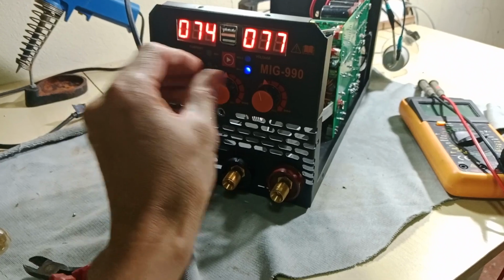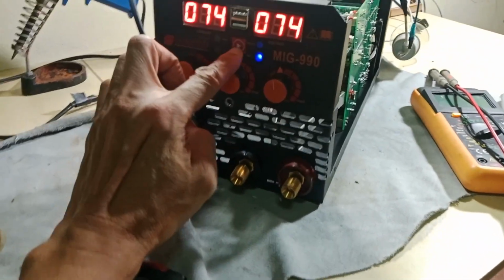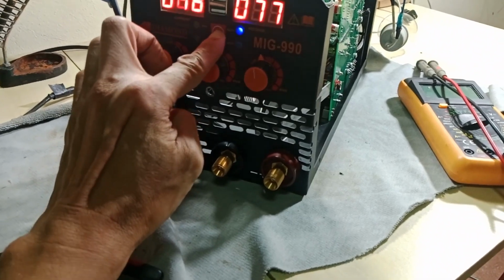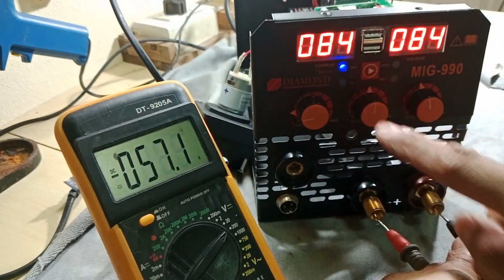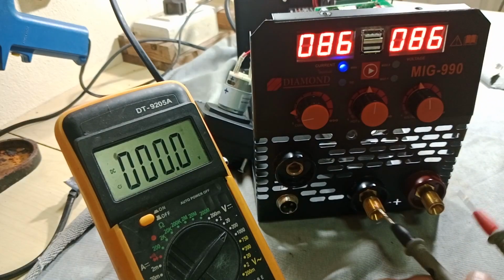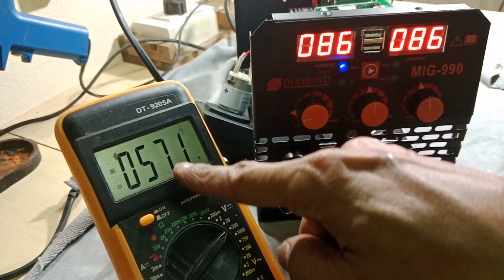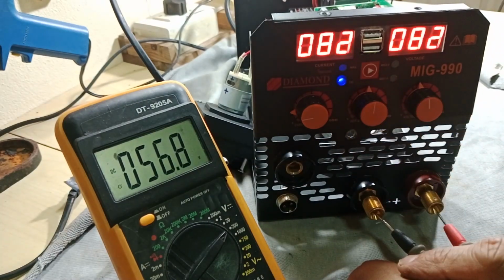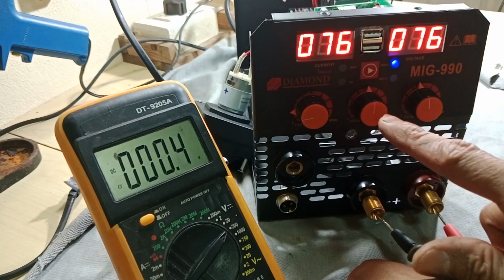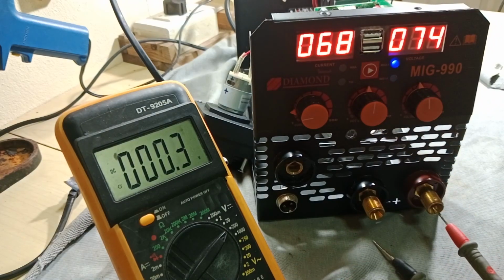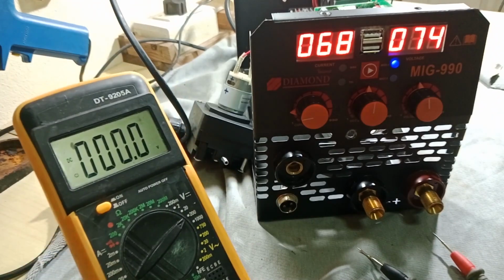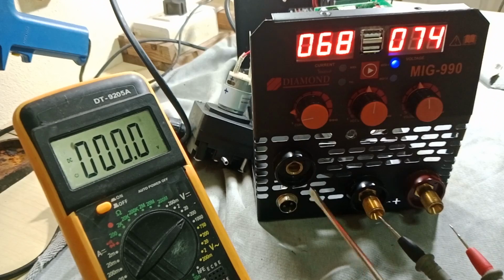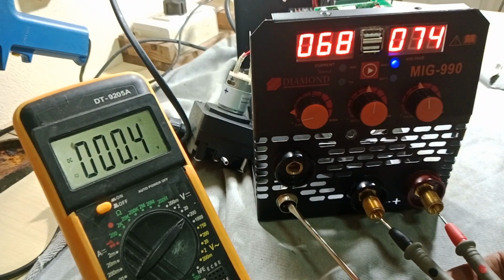Now that the power supply is working, we can almost assure that this welder is now working normally. There is a push button function selector in the front panel, and when I select to MMA function, we can see that there is about 55 volts DC in the terminals. When I selected the MIG function, there is no output voltage because that is to be turned on by the trigger switch at the torch. I will mimic the trigger switch by touching the leads with the screwdriver. And you can see that the output does turn on, and also the wire feeder motor rotates.